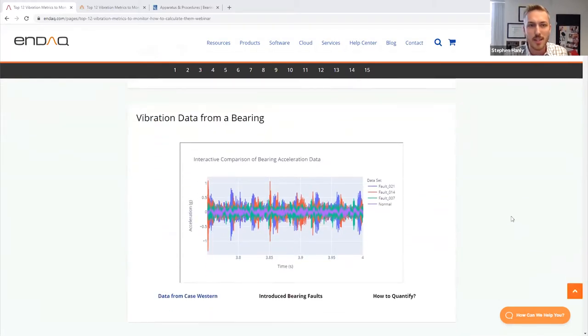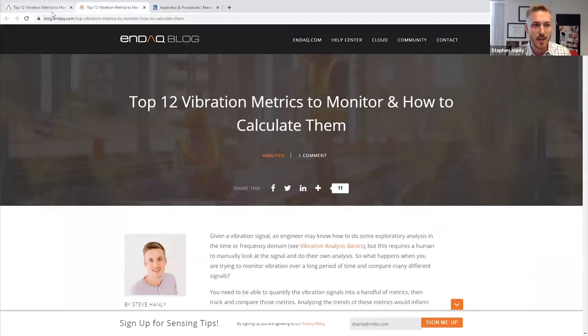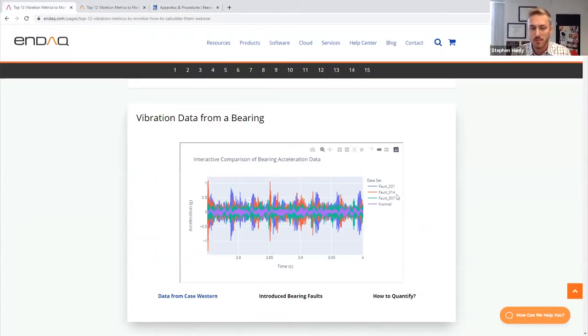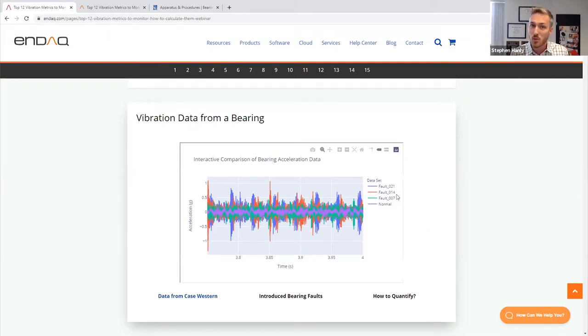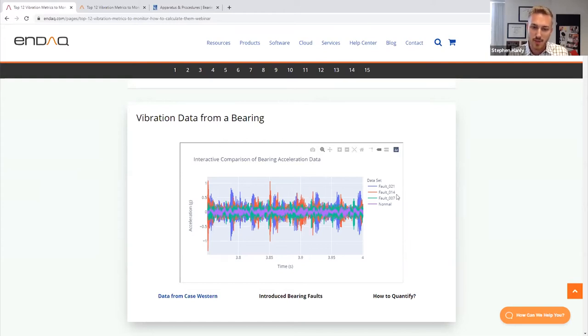The data we're going to look at today was generated from Case Western University, which shares this data on their website. They had a bearing with a variety of different accelerometers in the assembly, and they introduced a series of fault conditions and recorded that data. We're looking at four signals: the normal bearing and three fault conditions. These particular ones were when they machined a small hole into the inner race of a bearing. Fault 007 is a seven-mil diameter hole, fault 014 is a 14-thousandths-of-an-inch hole machined into the bearing.